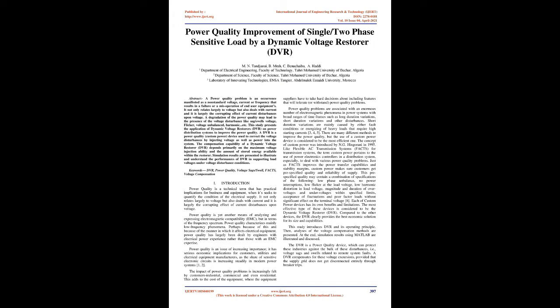The compensation capability of a dynamic voltage restorer, DVR, depends primarily on the maximum voltage injection ability and the amount of stored energy available within the restorer. Simulation results are presented to illustrate and understand the performance of DVR in supporting load voltages under voltage disturbance conditions. Keywords: DVR, power quality, voltage sag/swell, FACTS, voltage compensation.